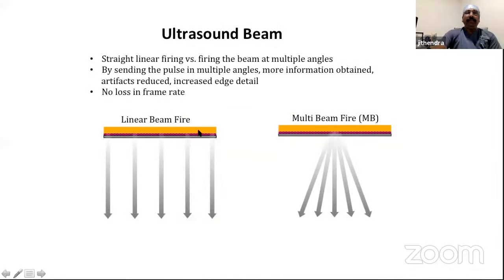Now it can be a linear beam fire or a multi-beam fire. The initial ultrasound machines all had a linear beam fire, where you see parallel beams of ultrasound waves going down and getting reflected back. To increase the clarity of the image, there's multi-beam firing, or multi-beam enhancement, which is incorporated into many ultrasound machines. That improves the quality of the ultrasound images being created.